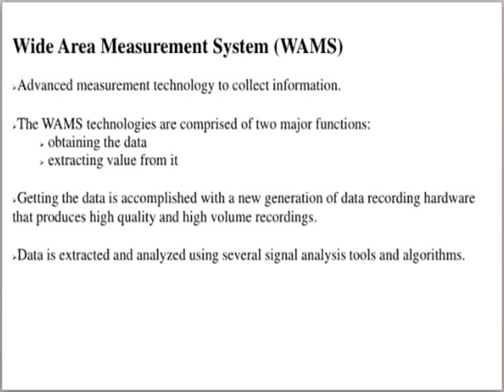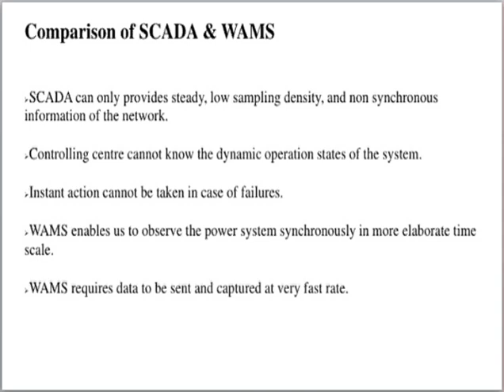Now, the differences between SCADA and WAMS. SCADA can provide only steady, low sampling density, non-synchronous information of the network. The control center cannot view the dynamic operation, only steady state operation, and instant actions cannot be taken from SCADA. WAMS enables observing the power system synchronously on a more elaborate time scale. Time is very important. It operates at a very fast rate, and WAMS requires data to be sent and captured at a very fast rate.